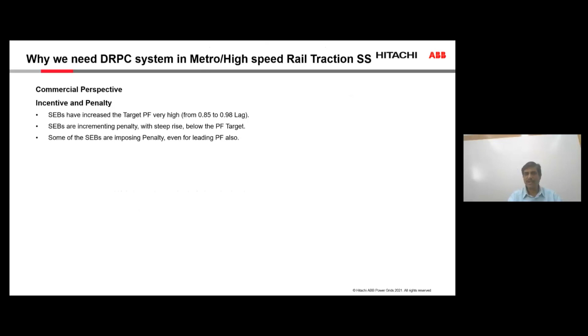Traditionally, it was said that lagging power factor will attract penalty. Nowadays, people have understood that putting in too much fixed capacitor can become leading power factor during light load conditions. So some SEBs have started to penalize both lagging power factor as well as leading. So we need to correct on both points. When there is a maximum demand exceedance, we all know traditionally that whenever we exceed the contract demand, we end up paying a penalty. That's also there. And then there are some good things also that SEBs are encouraging: when we go close to unity or high power factor, we also get a rebate on the electricity bills. These are huge savings when we talk about the operating cost of high-speed rail.